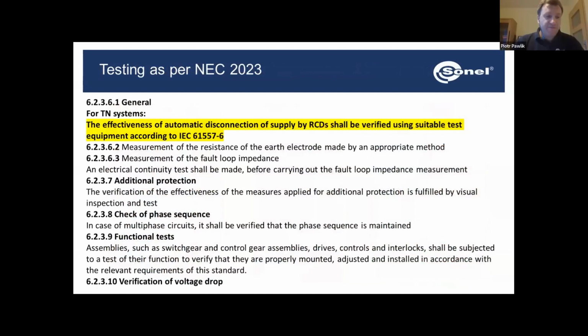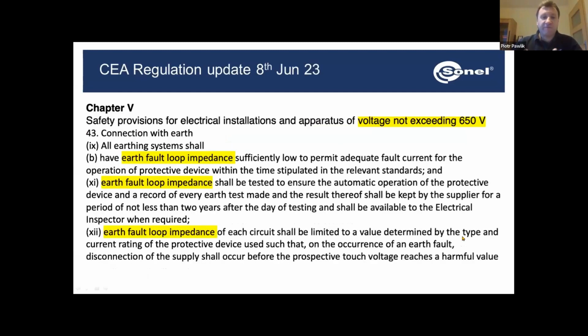All right. Now, if we look into the NEC, the National Electrical Code, we can find there that we have different levels of protection. There's basic protection, which means basically that the dangerous parts shall not be accessible, and accessible parts shall not be dangerous. For that reason, we use insulation on the live parts, we use some barriers and enclosures, or we put them beyond the reach of one's hand. Now, in case of a fault situation, the standard defines disconnection of power supply. For that reason, we're going to need to check fault loop impedance, and there might also be additional protection, like additional equipotential bonding, or the RCDs, which we also need to check and make sure that their parameters are okay.